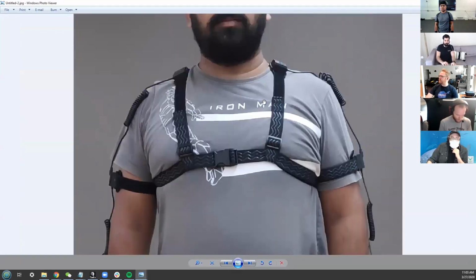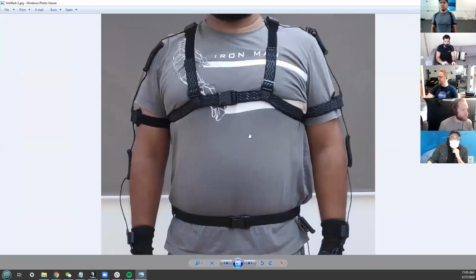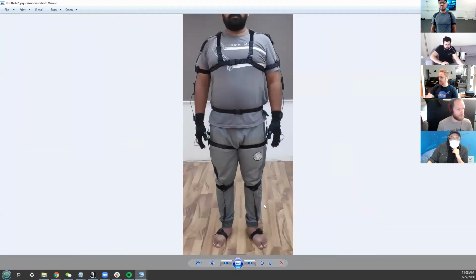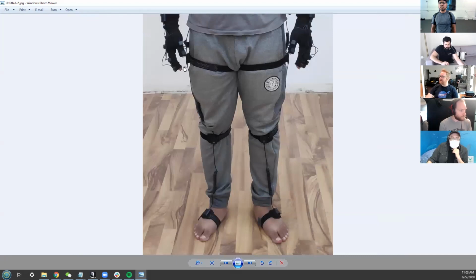Okay, another one: the user here put the sensors on top of the shoulders instead of on the upper back. Again, sweatpants, very baggy, so if they do anything other than basic walking, the clothing is going to start moving the sensors, which is going to cause them to slip and move and fall. Also, the thigh sensors here are set too high. They should be dropped about another 3 inches, so it's closer to mid bone. And the same problem here with the shin sensors. Right now, he's got them right under his kneecaps. That's a problem because they're too high. You want them lower on the bone. I say mid bone as general advice, but that's what you want to shoot for.